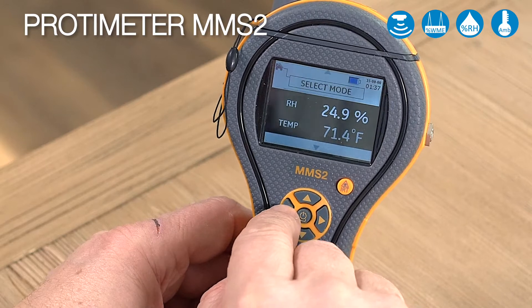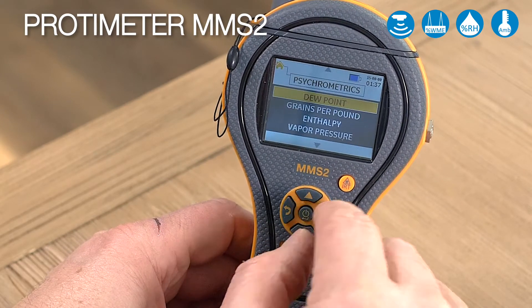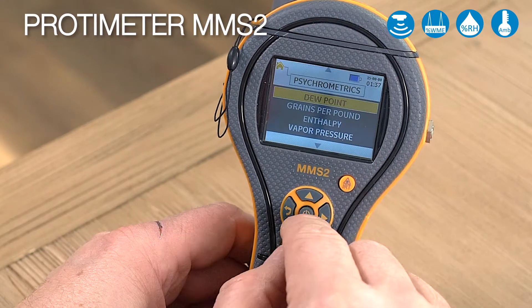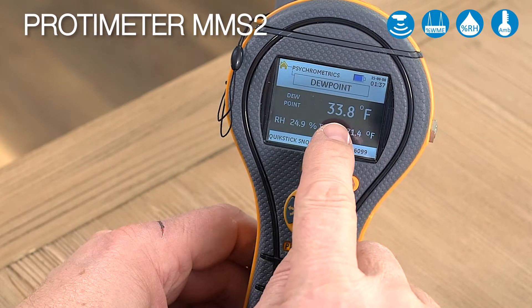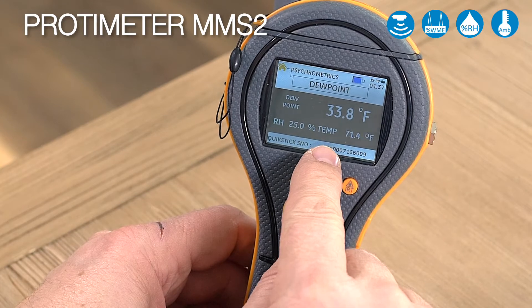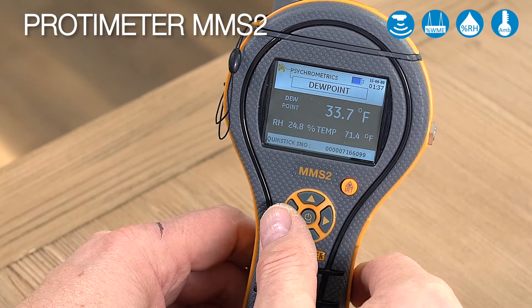The MMS2 will take a variety of different sensors including our Hygrostick and extended quick stick. Now we'll go back to the main menu and go down to our psychrometric mode. Here you'll see a secondary menu and you can choose whichever psychrometric measurement you want. Let's choose dew point — here we can see the dew point displayed in the large number, but it also displays relative humidity and temperature below, along with the serial number of the sensor used.